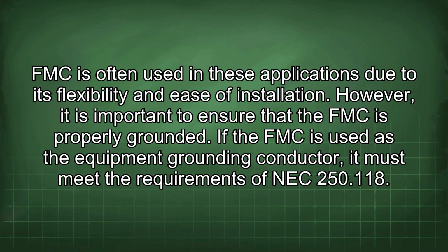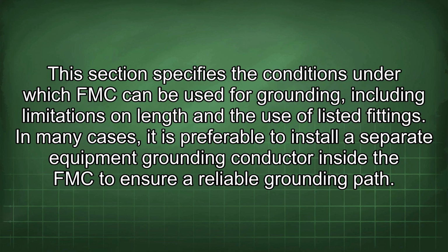If the FMC is used as the equipment grounding conductor, it must meet the requirements of NEC 250.118. This section specifies the conditions under which FMC can be used for grounding, including limitations on length and the use of listed fittings. In many cases, it is preferable to install a separate equipment grounding conductor inside the FMC to ensure a reliable grounding path.